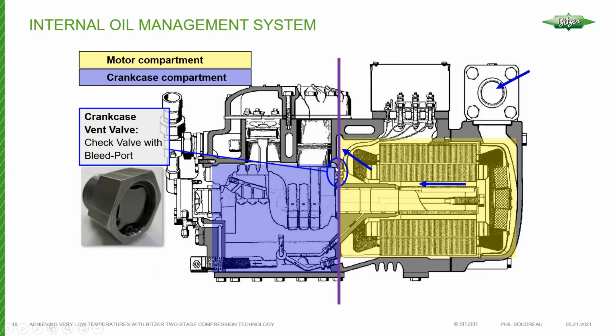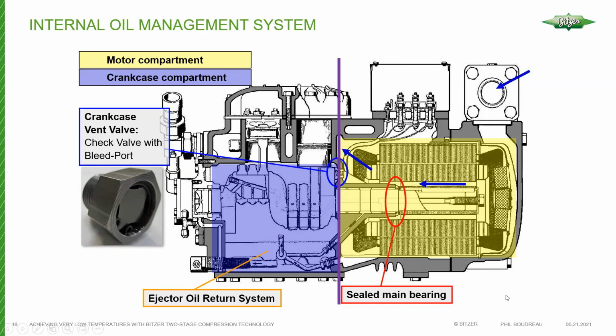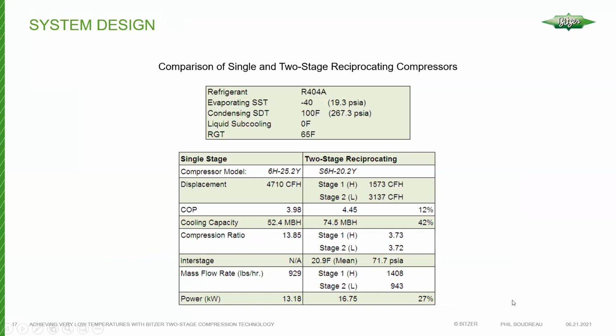And having the vent valves there really suppresses foaming. In the event that there's a fair amount of refrigerant in the crankcase oil for whatever reason, and it starts to foam up rapidly on startup, that would be a problem. The vent valves restrict the flow. So when the compressor starts up, the refrigerant slowly vents out of the oil or the crankcase area over to the motor barrel to suppress foaming. That's one of its main purposes. Okay, so there's a sealed main bearing here, and then we have the ejector oil system. This is no different than what's done in the single stage compressors.